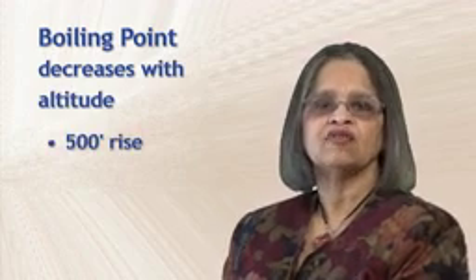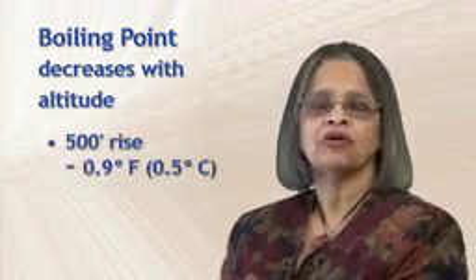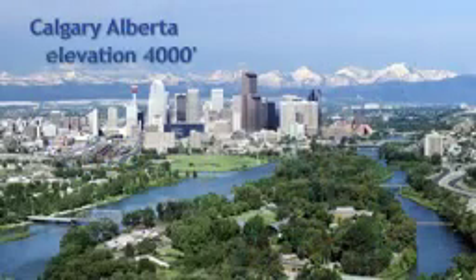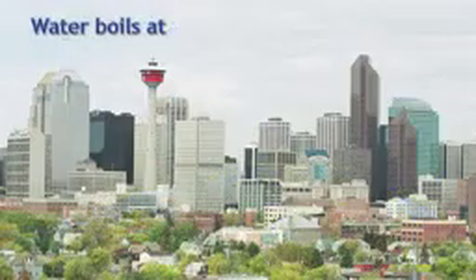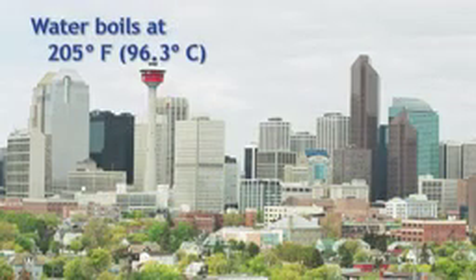We've been calibrating these thermometers in a plant in Vancouver at sea level. But for every 500 feet above sea level, water boils at nearly 1 degree Fahrenheit less. So in Calgary, which is 4,000 feet above sea level, water boils at 205 degrees Fahrenheit or 96.3 degrees Celsius. So it's important to find out the altitude of the plant where you work and calibrate your thermometers accordingly. If they are only out a degree, there's no worry, but more than that, you need to recalibrate your thermometers. There is a link to a sample calibration procedure that you can download and customize for your own operation.